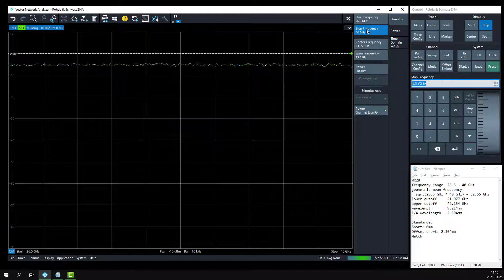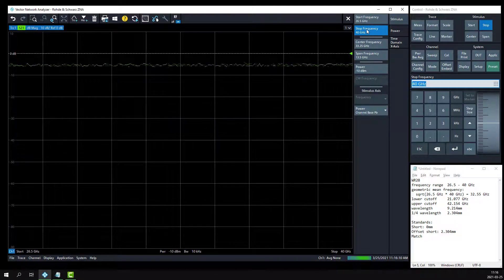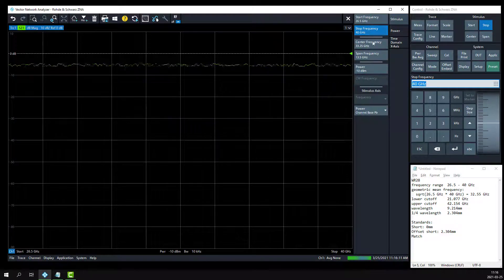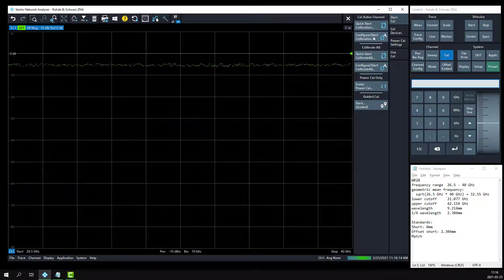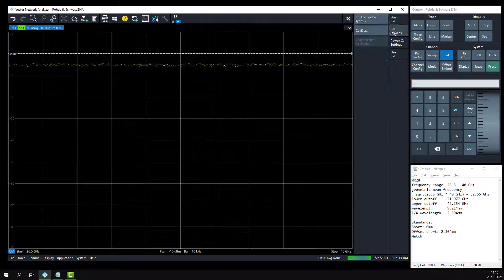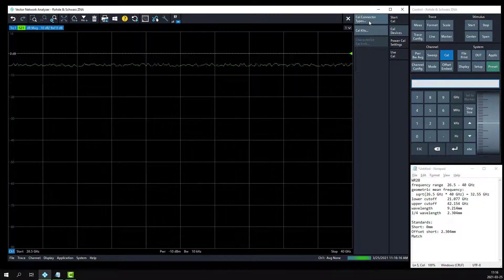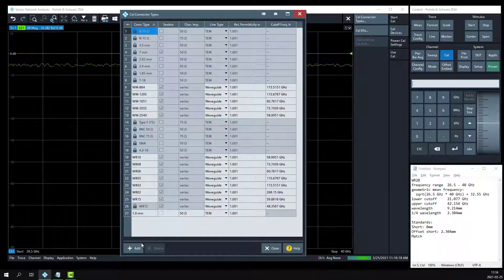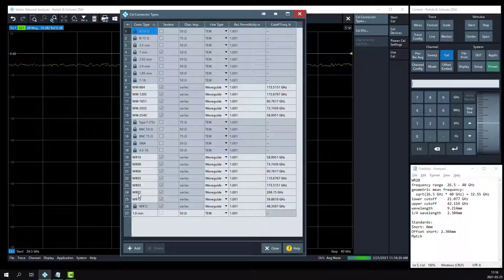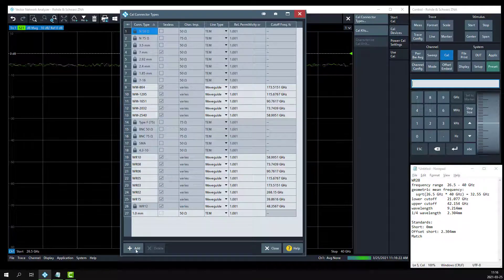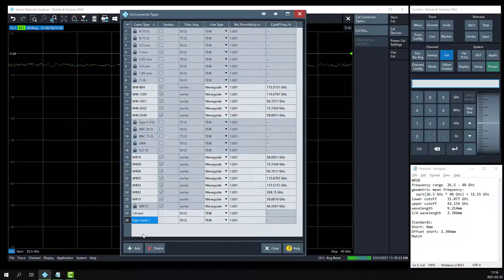The second step is to define the WR28 waveguide connector type. Click on the calibration hard key, go to Cal devices, and Cal connector types. We'll note that the WR28 connector type is currently not listed here, so we'll add that.